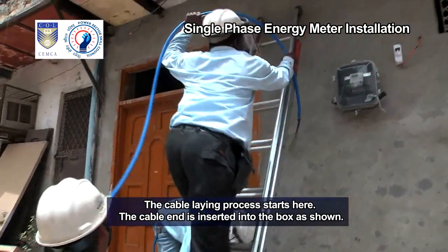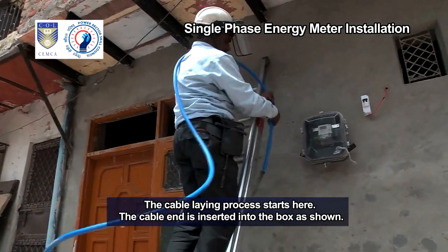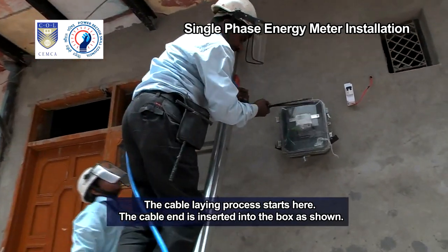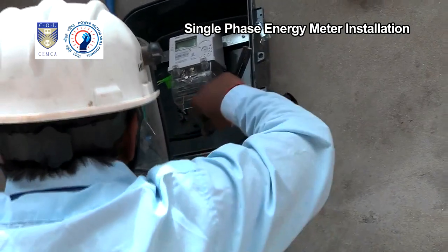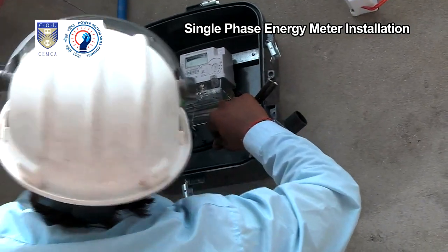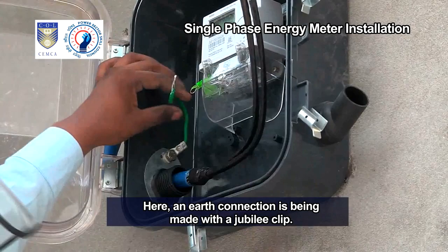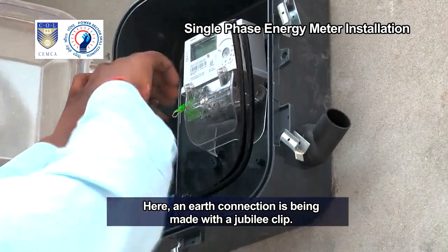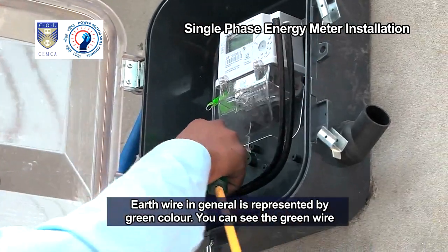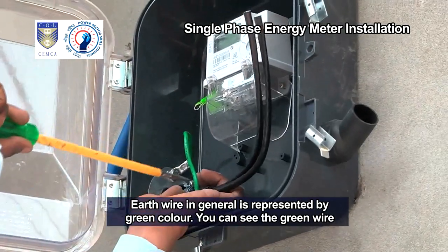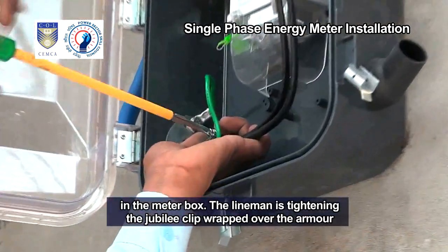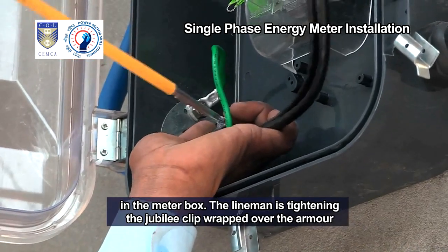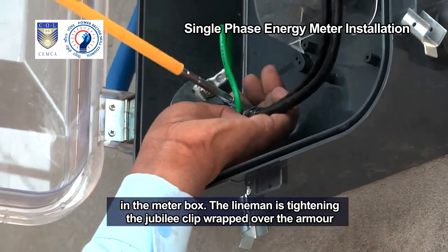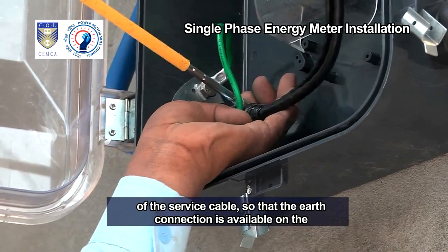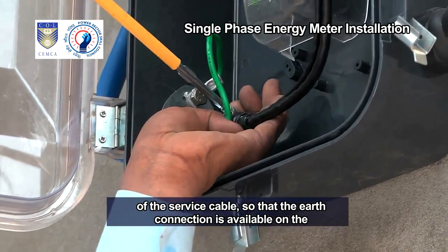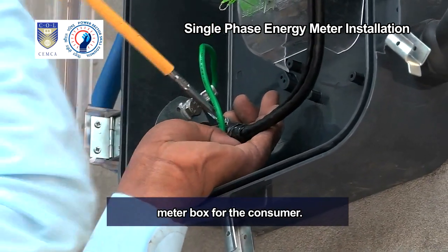The cable laying process starts here. The cable end is inserted into the box as shown. Here, an earth connection is being made with a Jubilee clip. Earth wire in general is represented by green color. You can see the green wire in the meter box. The lineman is tightening the Jubilee clip wrapped over the armor of the service cable so that the earth connection is available on the meter box for the consumer.